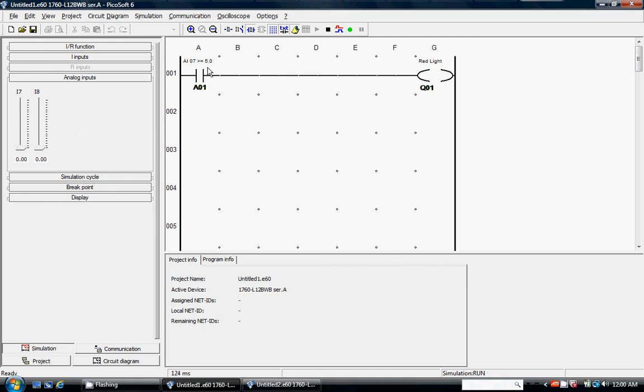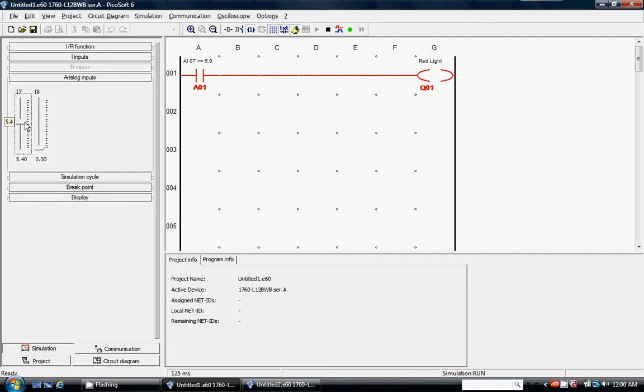And with my ladder logic here, if I click and drag the slider above 5, then the red light should come on. So if I do that, you can see here when I get to 5.0, it's greater than or equal to, the red light turns on. If I go just slightly below that at 4.9, it's not on. If I go to 5.0, it turns on because it's greater than or equal.